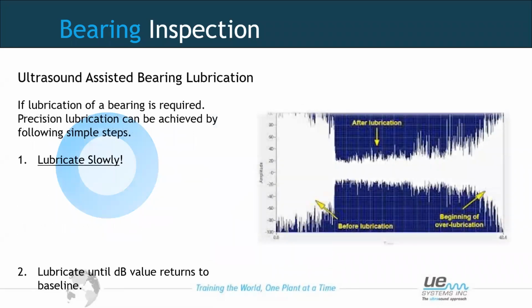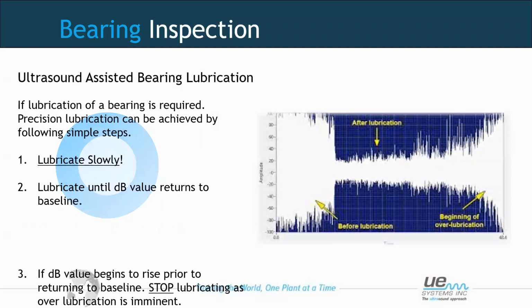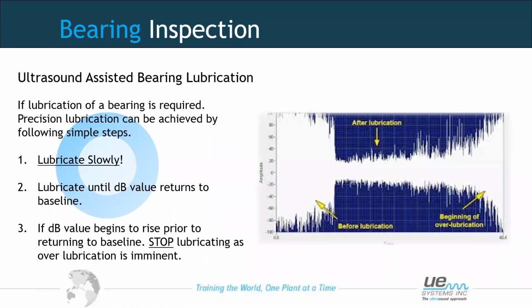So the main aim of this is to lubricate slowly. We lubricate until the decibel value returns to its baseline or as low as it will possibly go. And if the sound starts to increase, we know that we need to stop, because that is indicating an over-greasing of our bearing.